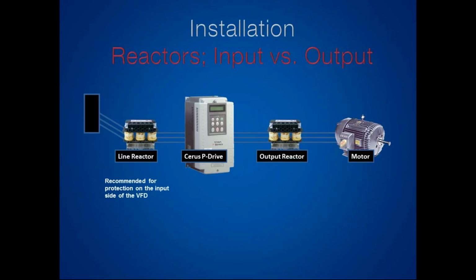Where we really see output reactors more would be in our pumping applications, so our groundwater and irrigation applications where a drive is mounted in a pump house and the motor is 200 feet down in a well below the water. I'm sorry, below the ground. That's where we're really going to see output reactors and output filters more often. But again, 100 feet is a good rule of thumb. If your drive is going to be mounted more than 100 feet away from your motor, go ahead and throw an output reactor on there as well.